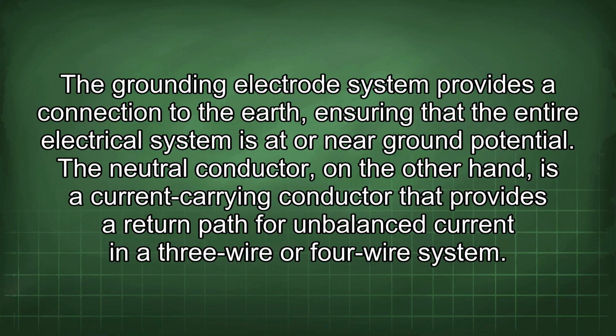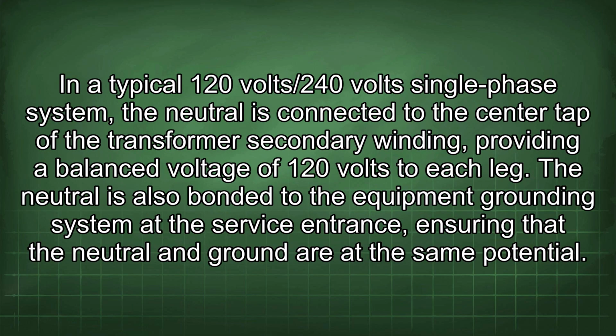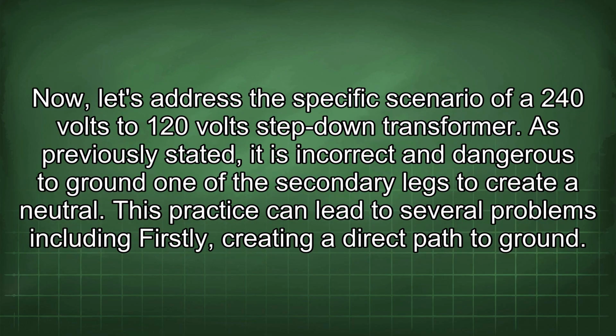The neutral conductor, on the other hand, is a current-carrying conductor that provides a return path for unbalanced current in a 3-wire or 4-wire system. In a typical 120 volts/240 volts single-phase system, the neutral is connected to the center tap of the transformer secondary winding, providing a balanced voltage of 120 volts to each leg. The neutral is also bonded to the equipment grounding system at the service entrance, ensuring that the neutral and ground are at the same potential. Now let's address the specific scenario of a 240 volts to 120 volts step-down transformer.